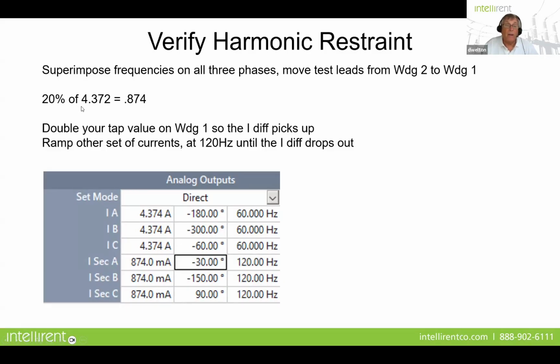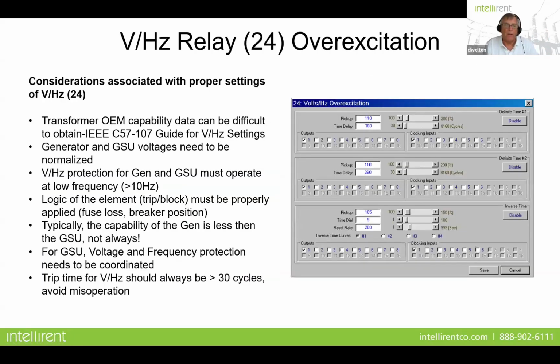Okay, and at 20%, 4.37, which is our tap setting for winding 1, it should drop out at 0.874 amps. Okay, so if we start with 0 right here, it's not seeing any harmonics, it's going to trip. So we're going to ramp up this current in milliamps until it drops out, and it should drop out. That means we have a second harmonic component greater than 20%, and that will keep the differential from operating. And you do the same thing if you have a fourth harmonic restraint enabled as well. Second is usually primarily what they use. Adding the fourth harmonic restraint just adds a little bit more security to the restraint on that element itself.